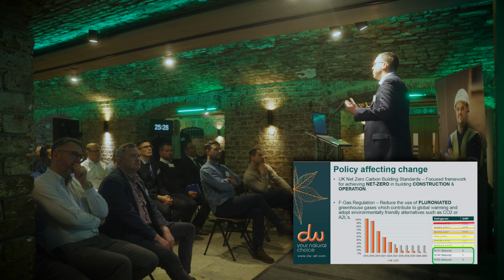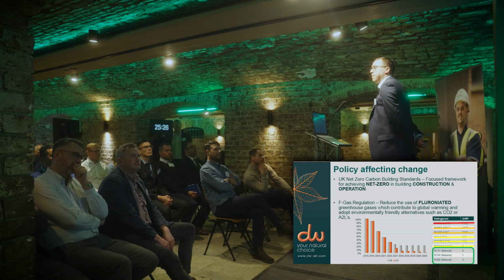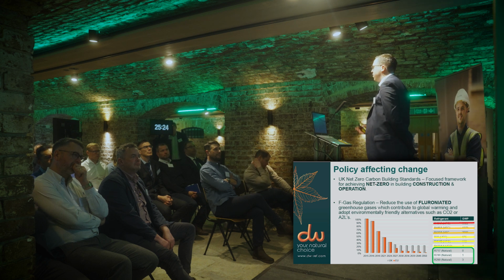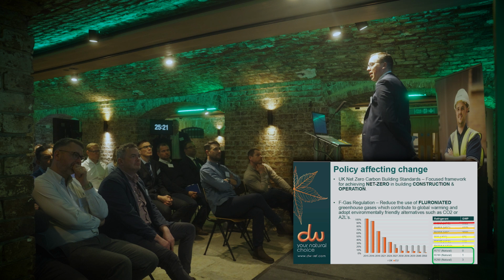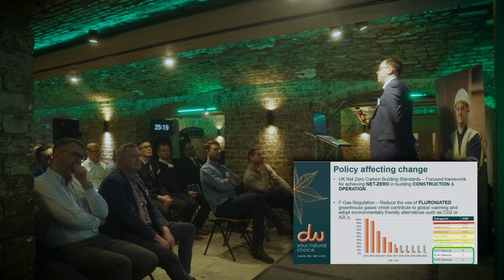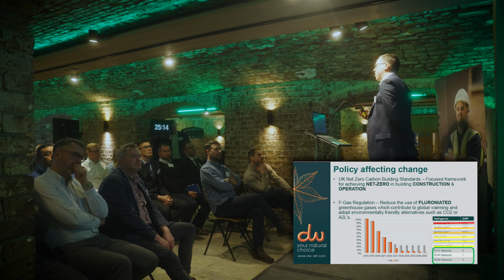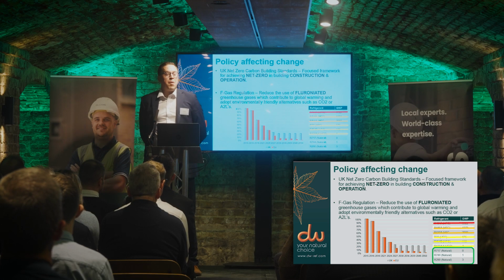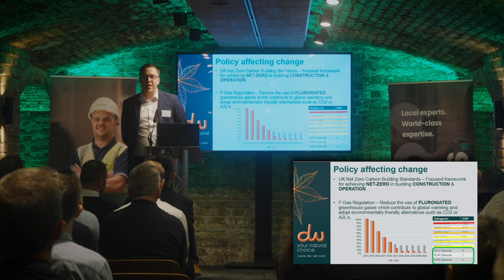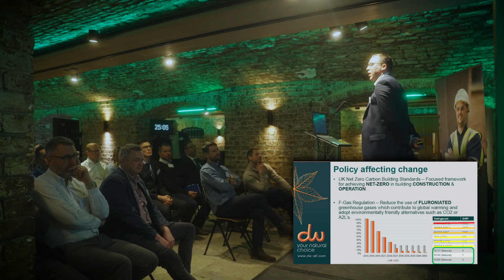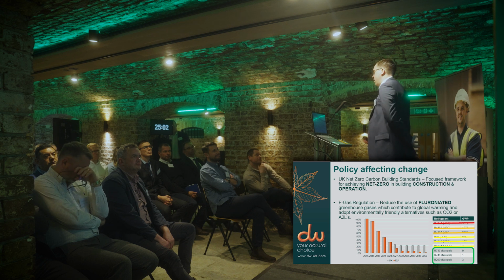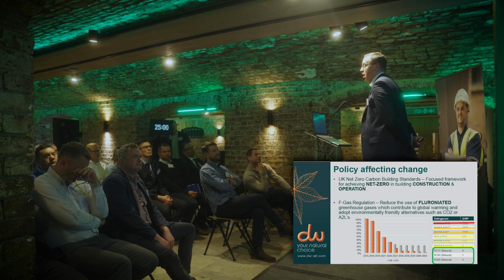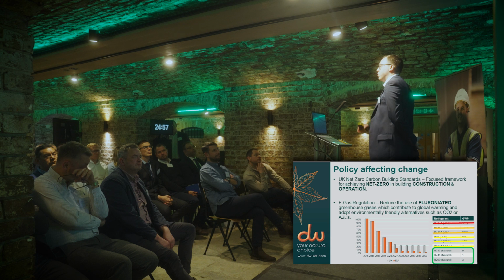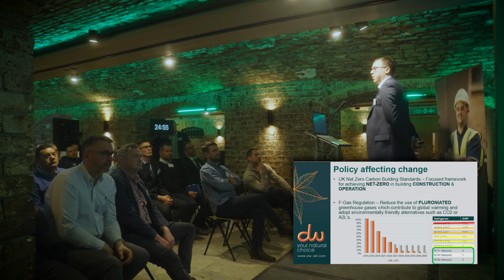We need to be transitioning to lower GWP alternatives. 410 R32 is a lower GWP version. 454B you're starting to see in some chiller applications and heat pumps as well. And then you've got YF, a refrigerant primarily used in car air conditioning, but with applications in chillers. By 2030, new systems on these gases might not be the right solution to future-proof your business, and that really leads us down the natural path - CO2, hydrocarbons and ammonia being the only real guarantee for the life cycle of your equipment.